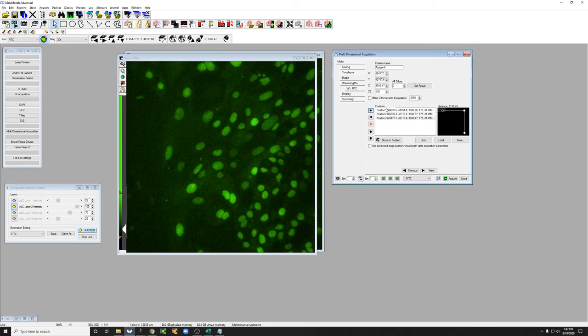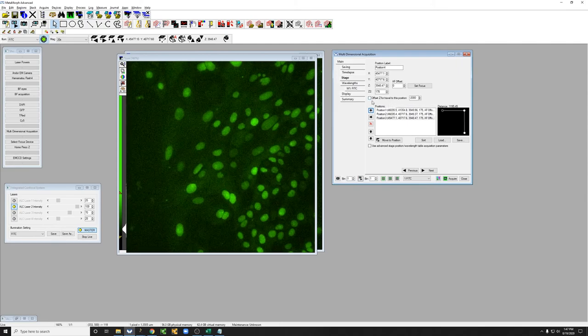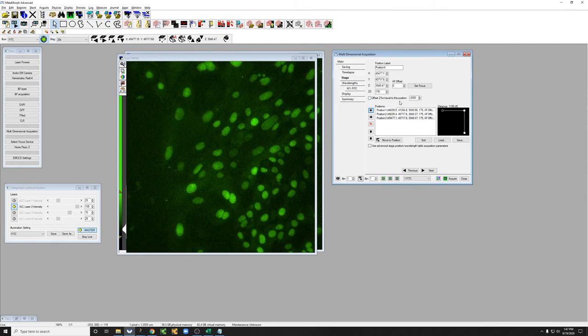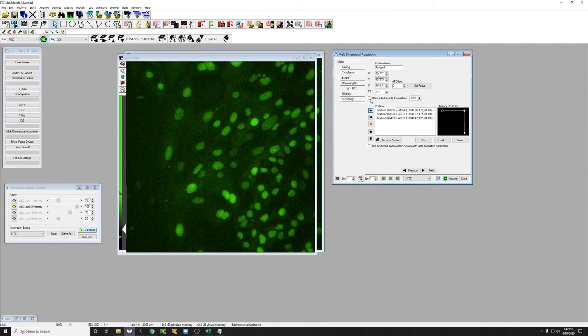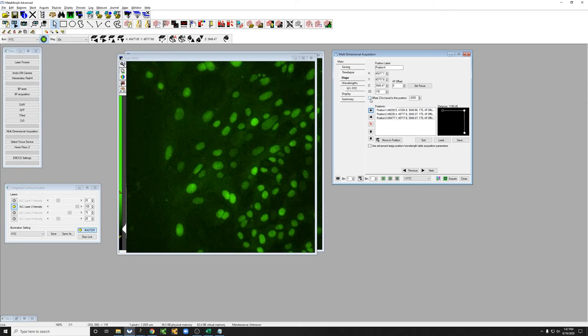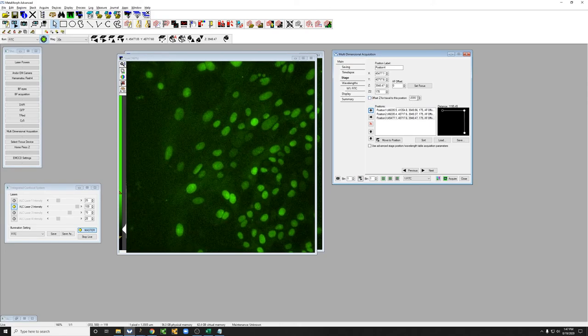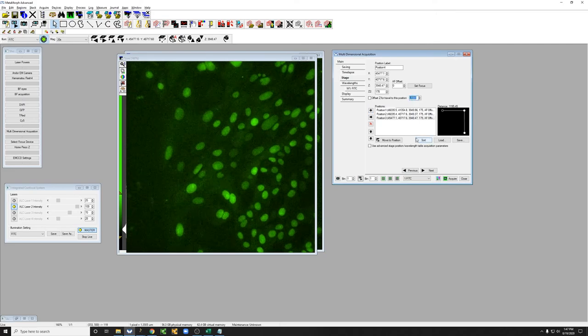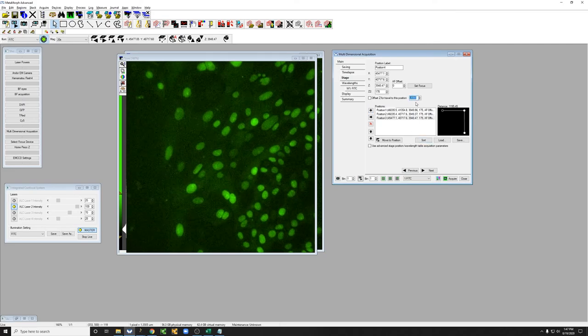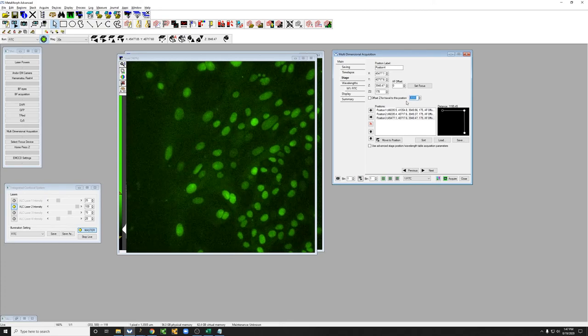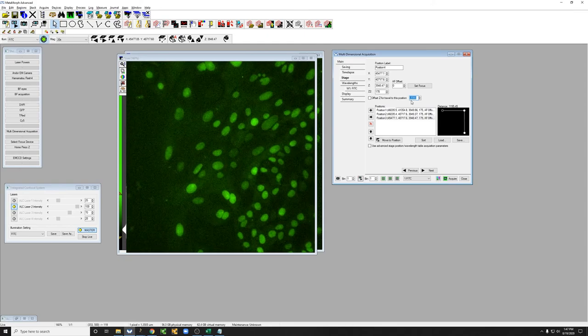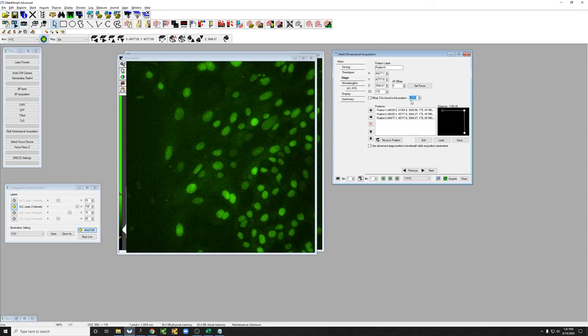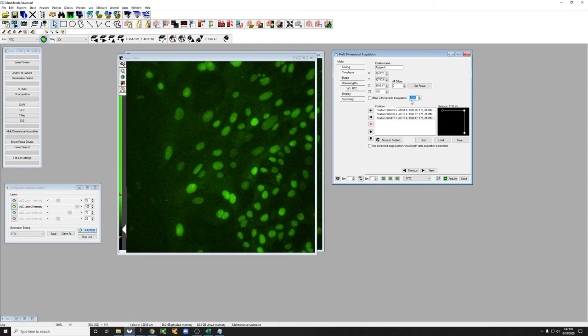So when you're using multiple positions, you can have the Z change as you're traveling to them. The software has a bit of a bug where even if you don't click on this, it will move the objective by this amount. So I recommend if you have an air objective, keeping this at zero. If you have an oil objective, talk to me about it, but it's a good idea to retract it. The oil objectives with multiple positions and time lapses have a lot of complications.